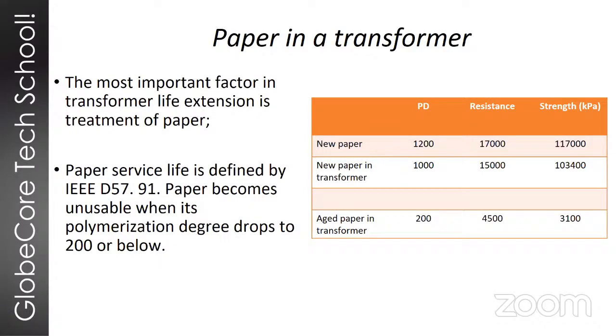And as the paper ages, the cellulose molecules break down and the polymerization drops. Normally, with normal aging, the polymerization degree is around 600 to 800. But as it falls down to 200 or less, that means the paper is basically unusable and unserviceable. And this is actually stated specifically in the standards by IEEE.